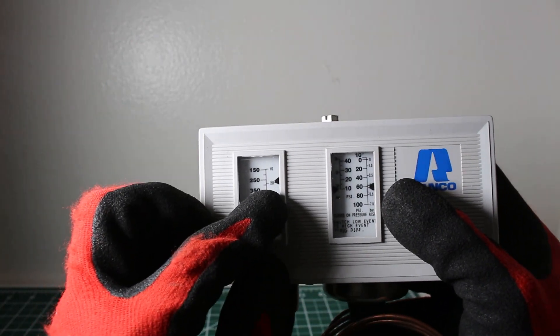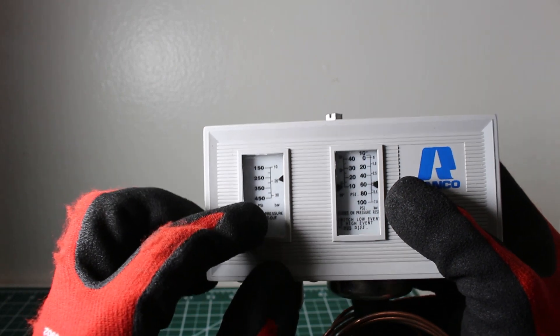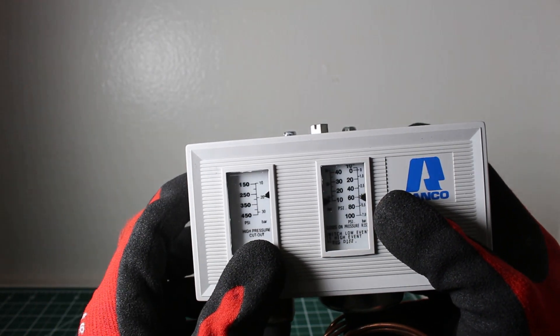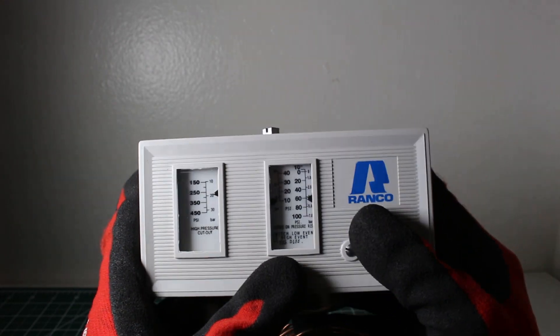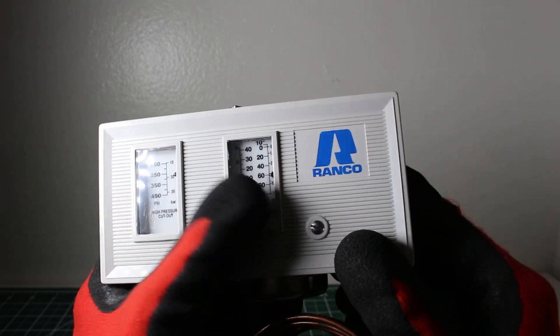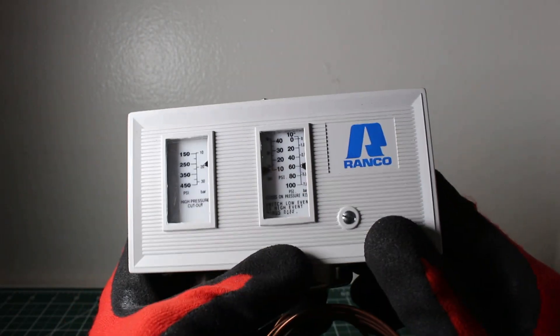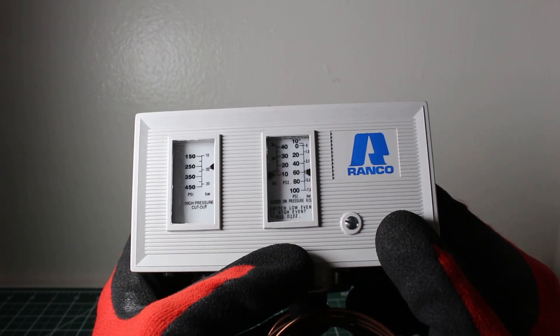On the high pressure side, there is just one black bar, one tab and you choose at which pressure do you want your system to cut out at. The low pressure control is slightly different. The low pressure control has two adjustments. Let's take off our faceplate to get a closer look.